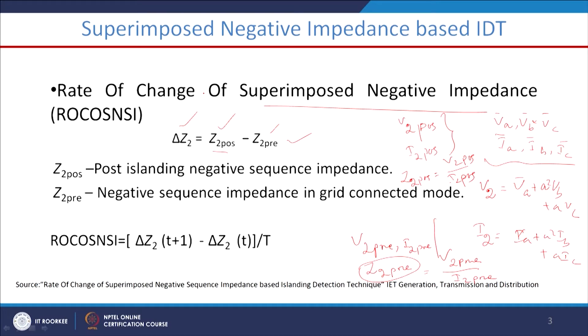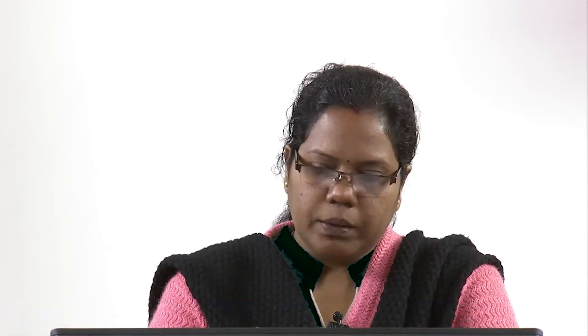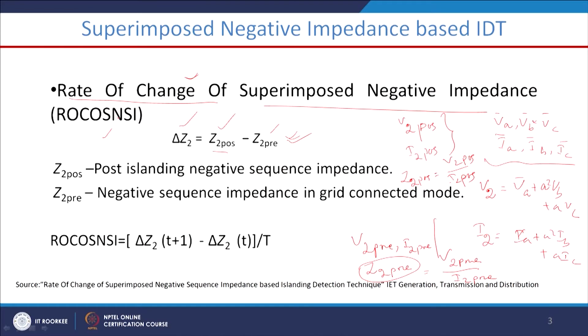If it is superimposed voltage: ΔV = V_post − V_pre. If it is superimposed current: ΔI = I_post − I_pre. In this case, we have taken the superimposed negative sequence based impedance, and we have further taken the rate of change of this superimposed negative sequence impedance — in short form: ROCOSNSI.